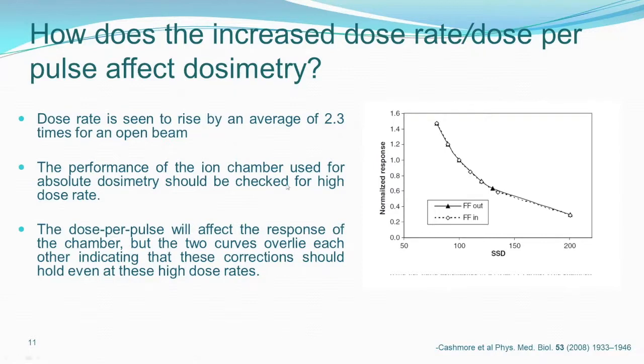The performance of the ion chamber at such a high dose rate has to be checked, whether your ion chamber can measure such a high dose rate. So you need to do a study. Significant information about this is given in the paper by Cashmore et al. in Physics in Medicine and Biology in 2008, where they studied the dose rate and dose per pulse effect for an ion chamber, I think, and they found that the response overlaps for double F and triple F, and there isn't much significant variation. However, it is good practice to check it for your ion chamber and your dosimeter.